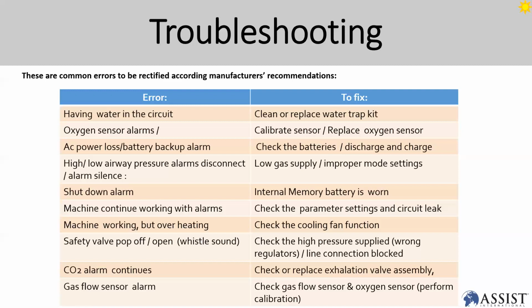Then overheat. Normally what happens is the ventilator fan is not working properly or the system has not been cleaned. So you get an overheating indication because of this type of problem. Sometimes the filter on your fan is not clean, so you get heat circulation inside the circuit. Then the safety valve popping off, opening, or whistling can be caused by high pressure, wrong regulator use, or a blocked line connection. Wrong regulator use is very common because people use the wrong type of regulator in the hospital. That can cause a lot of problems.